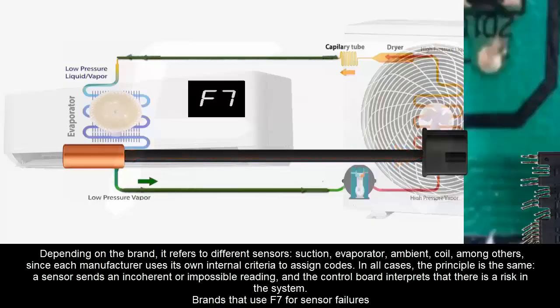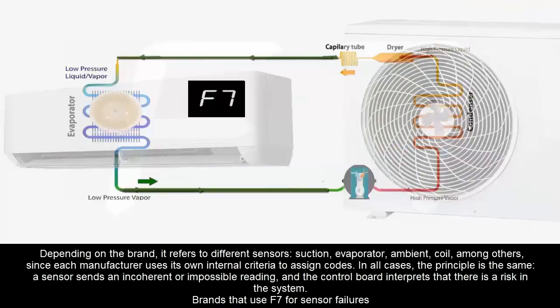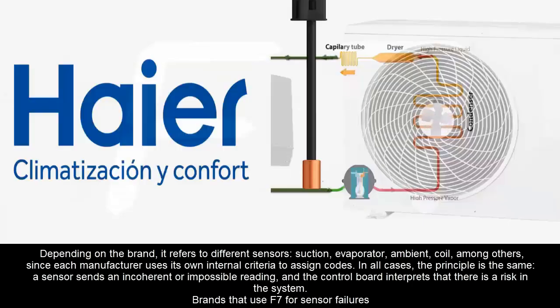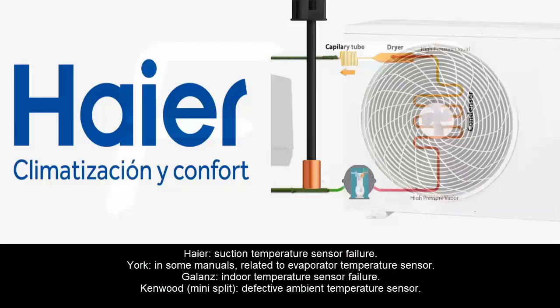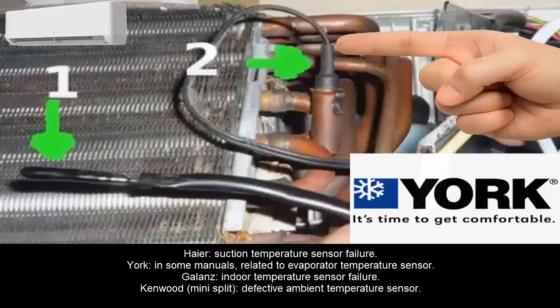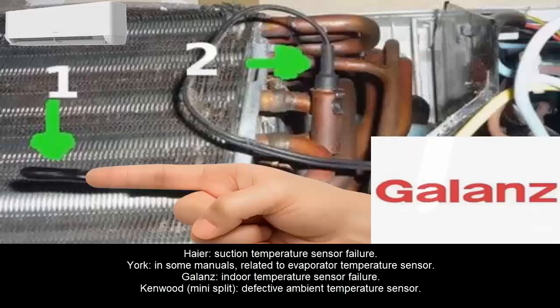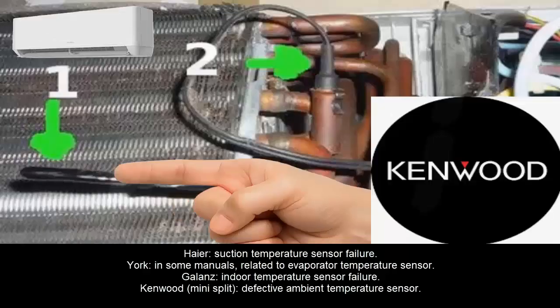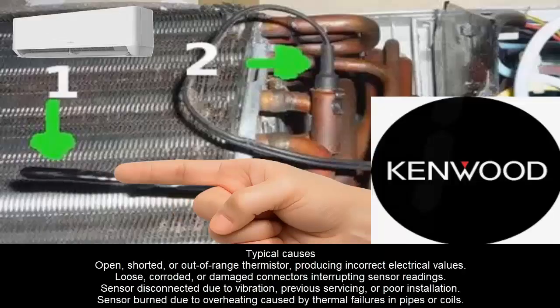In all cases, the principle is the same. A sensor sends an incoherent or impossible reading, and the control board interprets that there is a risk in the system. Brands that use F7 for sensor failures: Haier, suction temperature sensor failure; York, in some manuals, related to evaporator temperature sensor; Galanz, indoor temperature sensor failure; Kenwood, mini-split, defective ambient temperature sensor.